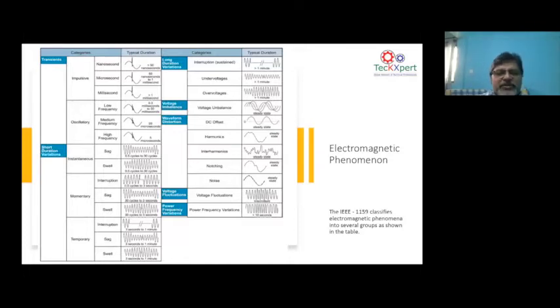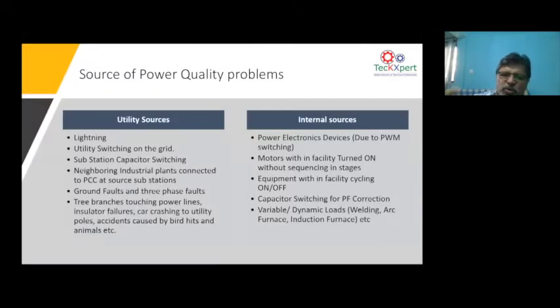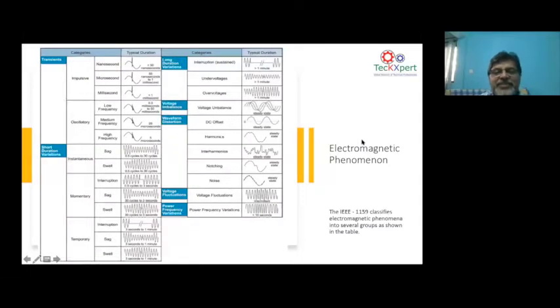Now, when you say long duration variation, this is very common: under voltage, over voltages. That's why many customers use OLTC on a transformer. So when you have an under voltage or over voltage, the OLTC functions and corrects the system. The OLTC does this because the under voltage or over voltage lasts for a few minutes. So an OLTC, as a mechanical device, can handle the under voltage and over voltages. Whatever I said here is all to do with voltage quality. That means when you draw power from the network, the voltage quality can be influenced by transients, short duration variation, and long duration variation.